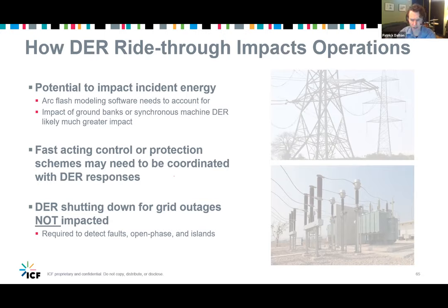I'm less clear on the amendment in 2014. We didn't talk about it here, but there was an amendment to IEEE in 2014 that allowed for voltage and frequency ride-through. It didn't require it, but it changed the settings a little bit, I believe, and definitely allowed for a wider range of settings, so that tripping wasn't mandatory at these very stringent default values that go back to 2003.